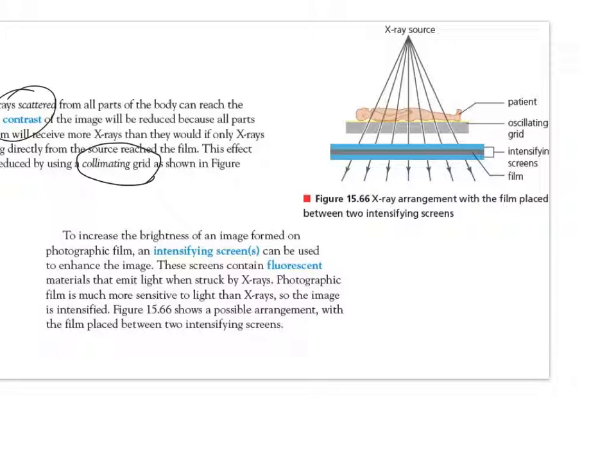Another way of increasing contrast by making the image brighter is by using an intensifying screen. These contain fluorescent materials that when hit by the x-rays, they emit light. Therefore the photographic film is not just receiving x-rays — it's receiving x-rays and the light given off by this fluorescent film, which is much more intense. So therefore your image is intensified.